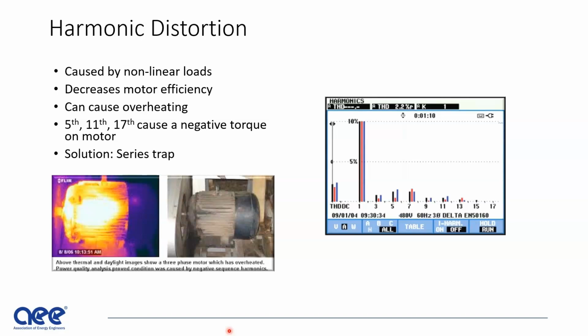Harmonic distortion, this is one of those hidden ones that affect most everybody and they don't even know it. The 5th, 11th, 17th, 23rd, these odd harmonics are actually negative torque harmonics. They create a negative torque. So if you have the presence of a 5th harmonic, which is pretty high energy in terms of these harmonics, you know, the lower the harmonic number, the higher the energy. So a 5th harmonic is actually creating a reverse torque that the primary 60 hertz has to overcome. In one case, we saw a motor that was designed to be loaded 63%. When we actually measured it and saw a significant 5th harmonic, it was loaded 143%, and it was burning out, and they couldn't figure out why when it was only loaded 63%. It was because of this harmonic.